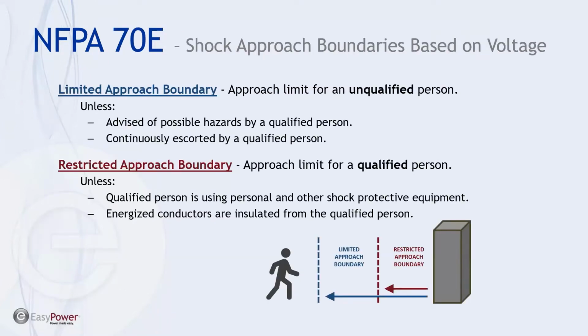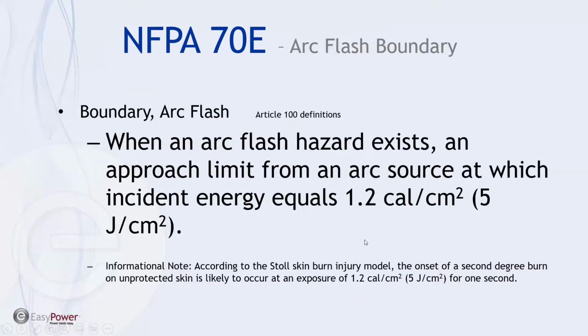NFPA 70E also approaches or talks about electroshock hazards, and these are a lookup table, if you will, based on the voltage on the exposed bus. It's probably important to notice that these boundaries don't exist when I have the equipment closed up. It's only when the door is open or the panel is removed that humans are exposed to bare conductors that are hot, and at which time these boundaries appear or become in effect.